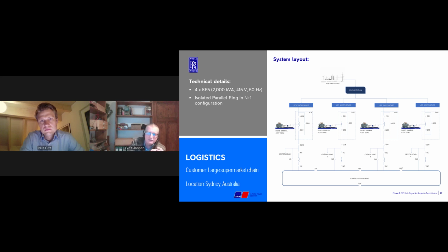So how we solve this challenge of the short circuit is by placing a choke downstream, close to the paralleling bus. You see that there is a bus, which is in fact a ring, but in the single line diagram, in the bottom, we have a ring, which is a paralleling bus. And each machine is connected to this paralleling bus through a choke that will limit the short circuit contribution of each machine. So that is a way of solving the problem of placing the machines into parallel by keeping the fault level at a reasonable level for the switchgears. And this type of installation, we are doing quite often where we need to have an N+1 configuration.